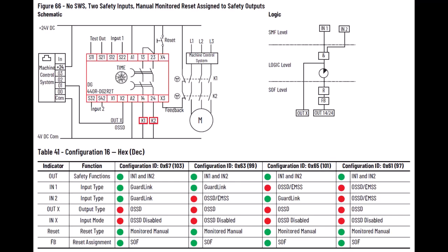You can confirm the operation by looking at the configuration examples in the user manual. This is in configuration 16 and has a value of 63 hex, which is 99 decimal. Looking at the logic, you can see that the out X turns on when both in one and in two are on. And you see that the safety outputs require both the feedback and reset signals to turn on and also applies the time delay when turning off.